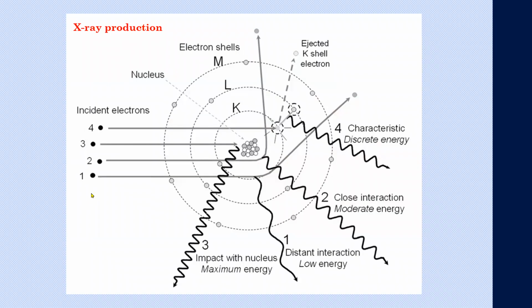So these electrons, when they collide with the target, can be deviated at very small angles or very large angles, or completely backscattered. And in these collisions, the energy that is lost by this deviation of the electrons is converted or transformed into photons with lower or higher energy. Also, the electrons can collide directly with one of the electrons in the inner shells of the atom, and the electron is ejected, and a vacancy is left. So one electron from the upper shells tends to fill this vacancy, and the difference in the energy from one orbit to the other orbit is transformed into a discrete energy photon.